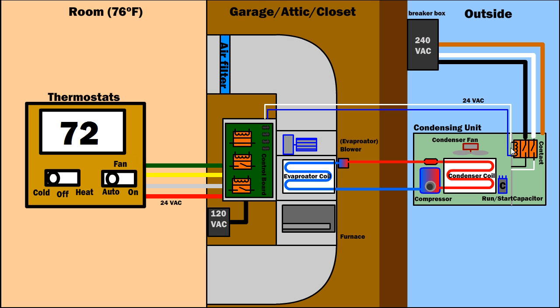And previously I gave you a link, I'll give you a link to that video again down here. You do want to measure 24 volts AC right here. If you don't have 24 volts AC right here at the contactor, that means that either this wire right here is damaged or once again the controller board is damaged or maybe the thermostat is damaged. But that's basically the next step that I would always check is the 24 volt AC because you have to have that in order to make the condensing unit come on.